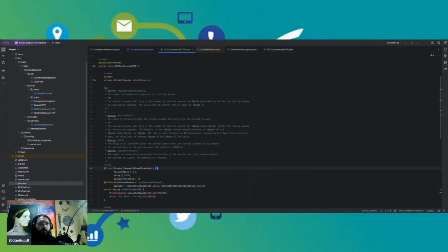The next parameter here is the delay. The delay represents the time that the circuit breaker will be open until it runs the algorithm and checks whether it should change from open to half open or from half open to closed. So this is the delay time. It's in milliseconds, so it means I'm just letting my circuit breaker run like that for 15 seconds.